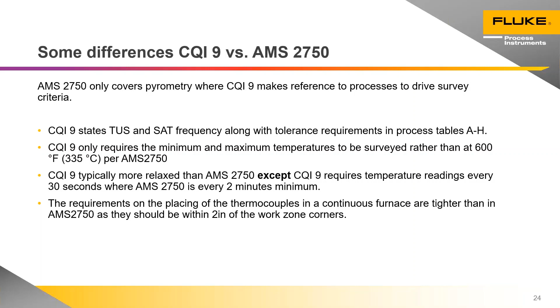And one note on the subject of continuous furnaces before we finish off for today is that in CQI 9, the requirement is that the thermocouples are within 50 millimeters or 2 inches of the edge of the working volume, whereas right back at the beginning of this presentation, I was mentioning that AMS 2750 continuous furnace thermocouples must be within 75 millimeters of the edge of the work zone. So there are some minor differences. The two are similar in many ways, but well worth bearing in mind. And I'm sure those of you that are using CQI 9 will understand only too well these differences.